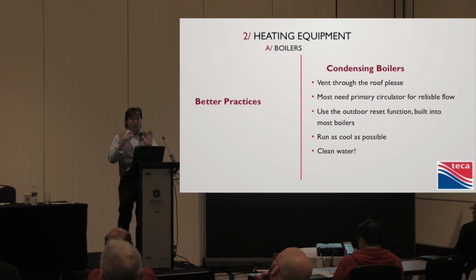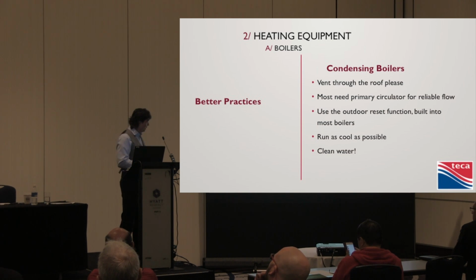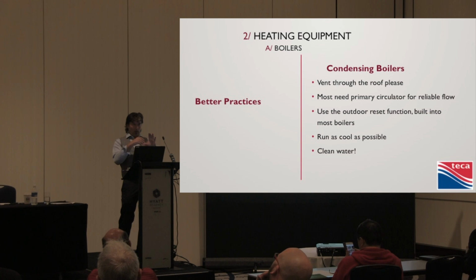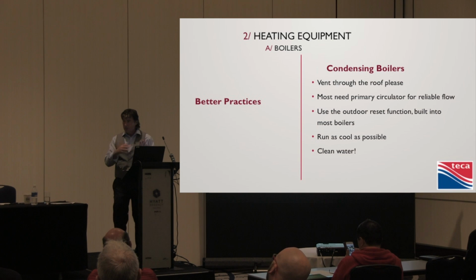The boiler says, you give me a good constant flow, you size a pump that can deal with my heat exchanger, and I'll modulate accordingly. So that's what we want to make sure we do. That means if we're using a dedicated pump for the boiler, let's not try to go out and do the whole house with it either, because it's sized to do the pressure drop of the boiler, not sized to do the pressure drop of the house.